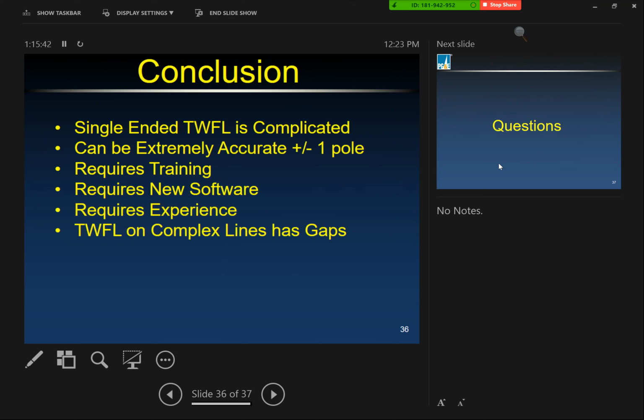In conclusion, single-ended traveling wave fault locating is complicated, especially compared with a double-ended method, where you're just taking two timestamps and plugging them into a very simple formula. Single-ended fault locating looks like very complicated forensics at that point. It can be simple, but it can definitely lead to head scratchers, especially with complex line topologies. But if it works for you, it can be extremely accurate. It's pretty awesome giving, with confidence, a fault location out on a 60 kV tap, knowing you've got to go right to that structure plus or minus one structure.